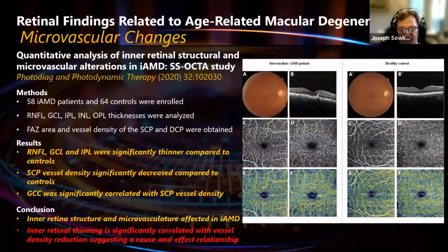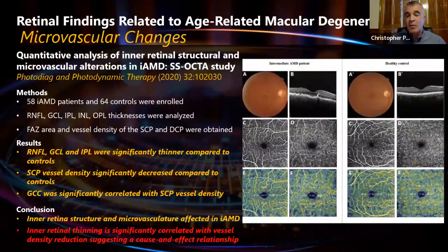So the microvascular changes, because this is that one where I had mentioned OCTA, it's coming. It is out there now in a number of devices, and OCTA normative databases are now being embedded within these devices. So now, just to whet your appetite, so to speak, swept source resolution is almost twice as high. So you can get down to the almost 2 to 3 micron level.